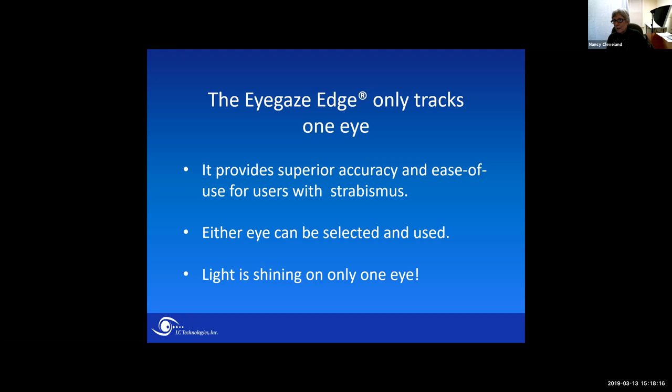We only track one eye. This is something we thought about 30 years ago — we assumed that some users would not have two functioning eyes, and depending on two eyes might be a dangerous route to go down. So from day one our systems have tracked one eye. We have binocular systems too, but it's not necessary — the difference in accuracy is negligible for this application. For somebody with strabismus, you're only tracking one eye, so you don't run into issues of which gaze point is really the gaze point. Either eye can be selected and used, and we're only shining light on one eye, so it's less fatiguing.